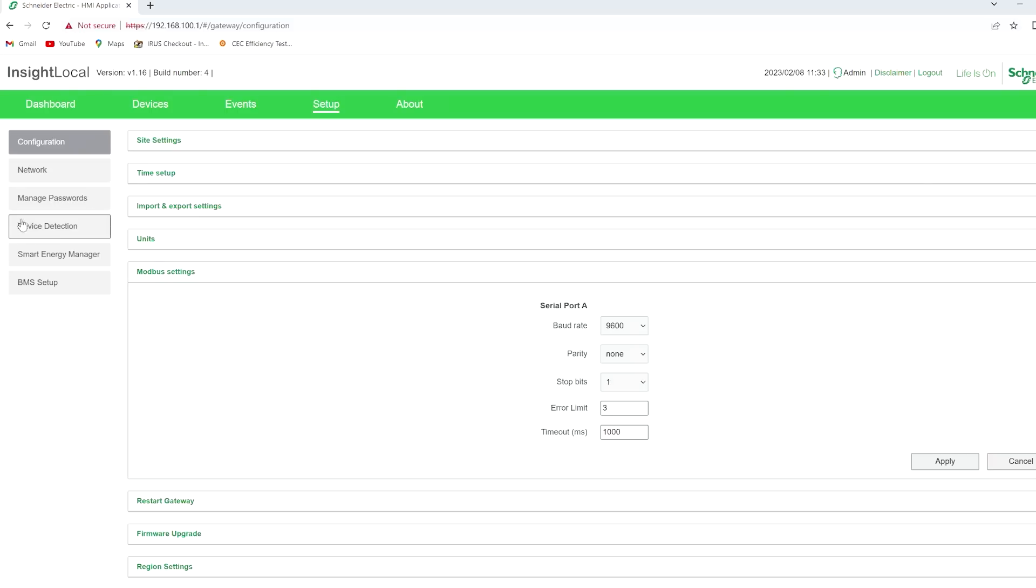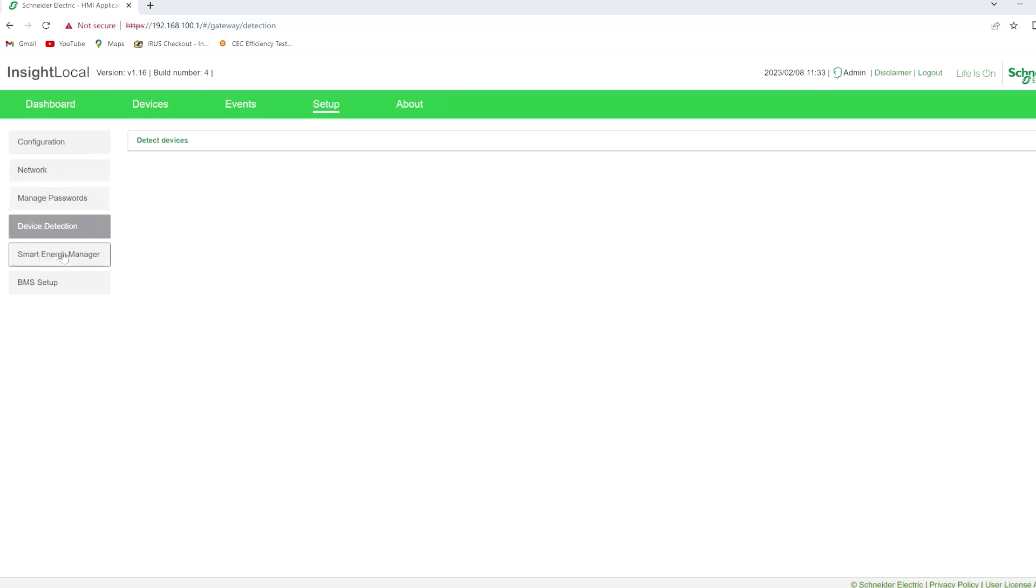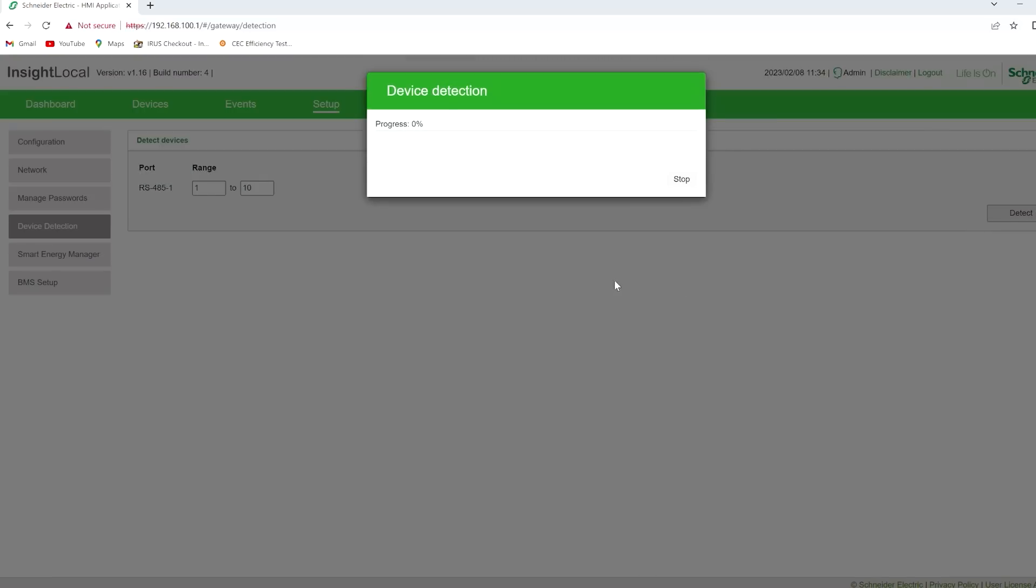Next we'll click setup in the upper right. Modbus settings. We're at 9600, so that's correct. That's good. And we'll click device detection. So next we go to device detection. Range 1 and 10. And detect. And it's not moving right now, but hopefully it finds the BMS. So we just have to wait and see if it finds it.